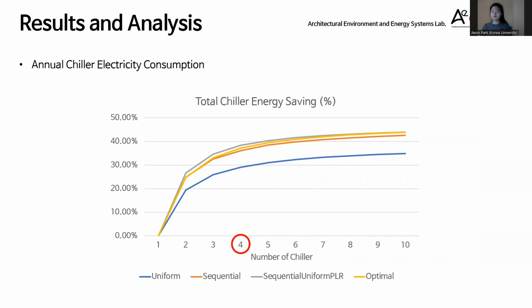However, the magnitude of the effect gradually diminished, and it was determined that a balance between the difficulty of maintenance due to the increased number of chillers and optimal cooling energy savings was achieved when using four chillers. In other words, for the weather conditions in Korea and a medium-sized office building, using four chillers with the SequentialUniformPLR algorithm resulted in approximately 40% of annual energy and cooling energy savings.